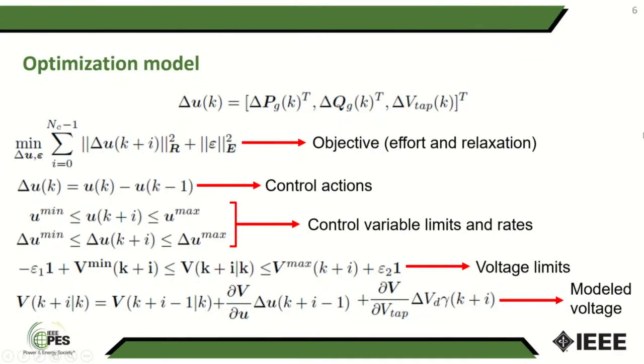Here we have a summary of the optimization model. The control vector is composed in this work of the set points of the generators, that would be P and Q for the active and reactive powers, and the taps of the main transformer. K denotes the present time sample, and I the future samples of the prediction horizon. The objective function, as mentioned previously, aims to minimize the magnitude and the number of control actions taken to correct the voltages, and it also includes a term of relaxation to guarantee a feasible voltage solution in case of extreme conditions, which is highly penalized.